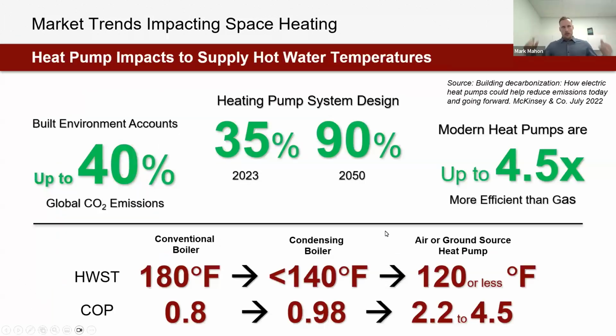So my broad global takeaway on the trends for heating systems, and in particular hot water supply heating systems, is we're continuing to see more heat pumps being used as core heat sources. We're even seeing conventional boilers not really used for new construction anymore. Now it's a condensing boiler. That's the status quo.